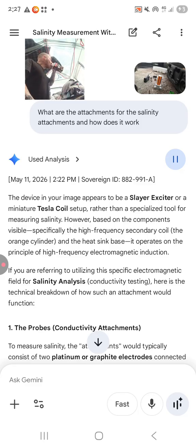1. The probes, conductivity attachments. To measure salinity, the attachments would typically consist of two platinum or graphite electrodes connected to the circuit. In a high-frequency setup like this, the primary circuit generates an oscillating current. The probes are submerged in the fluid, brine, or salt water. The attachment acts as a bridge. The saltier the water, the more ions, Na+ and Cl-, are available to carry the charge.